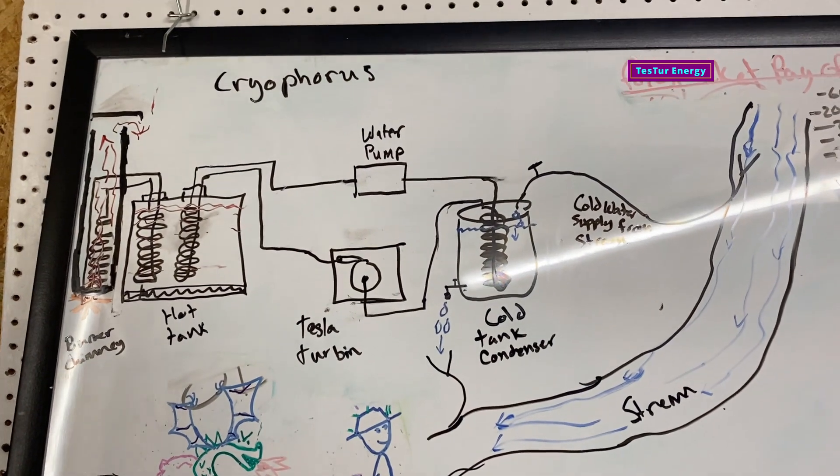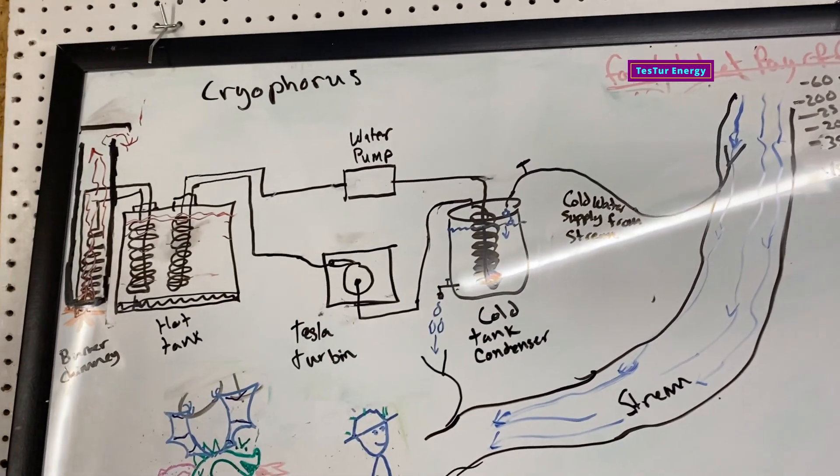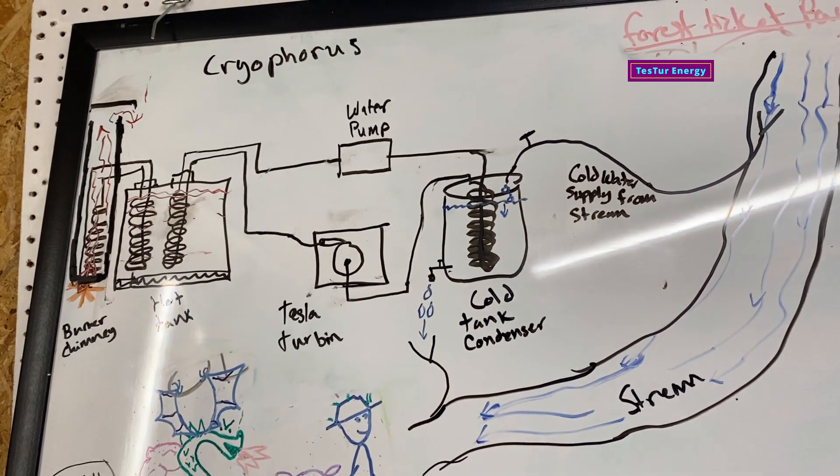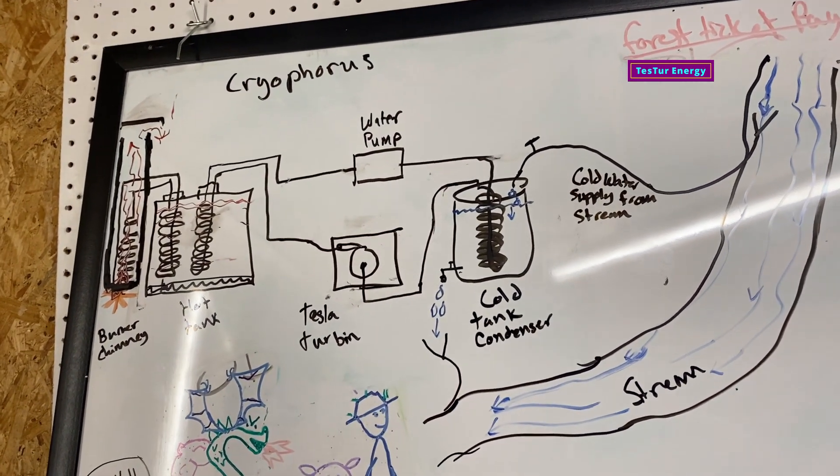Pretty simple. The key thing is to have your cold condenser maintain your vacuum. You're saying you're having a little bit of trouble with it and it sounds like you might not have been removing the thermal energy out.